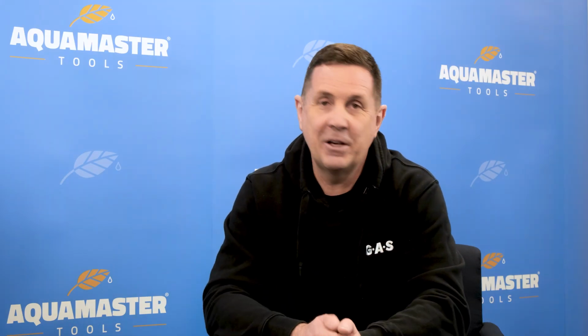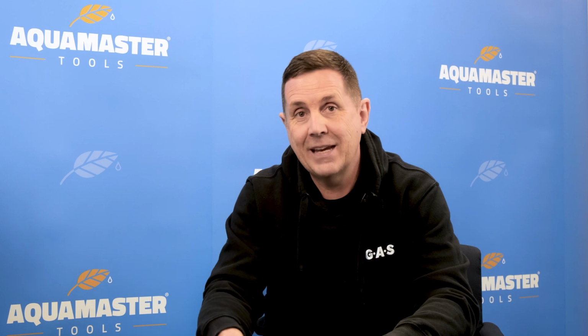And I want to give everybody a bit of a tip, what Pim's told us, and I know everybody does this because I know I do this. When you're calibrating the probes, you're dipping them in the solution, you're taking them out, then you dip in the next solution, you calibrate, you take it out. Every time you move it from calibration fluid to calibration fluid, you're contaminating them all. So what Pim was doing earlier when we were calibrating some pens: put them in water, clean them off, take them out, do a calibration, take them out, wash them again before you move on. Preferably with distilled water, because there's no nutrients inside, and that's actually the only way to clean them.